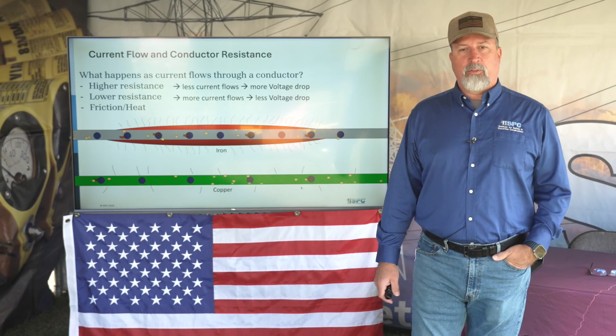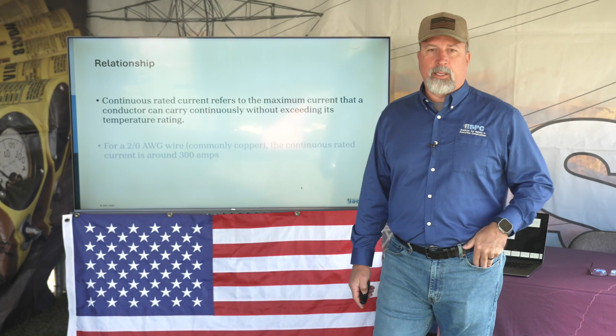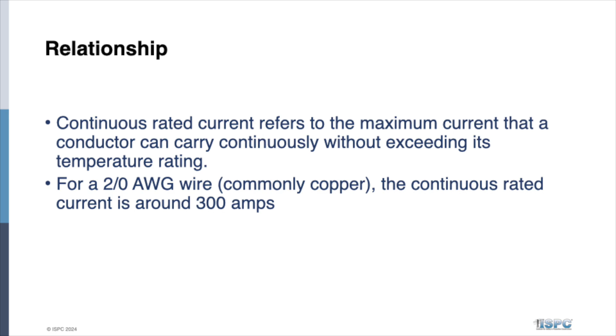All right, continuous rated current refers to the maximum current that a conductor can carry, okay, without exceeding its temperature rating. So all conductors have a max current that they can carry, okay. Again, most people, 2-aught AWG wire is commonly copper. On the line side, the overhead side, underground side of our system, it's normally the standard size temporary ground that we use, right? 2-aught. Get into the substations, it jumps up to 4-aught. 300 amps is what that 2-aught ground can carry.